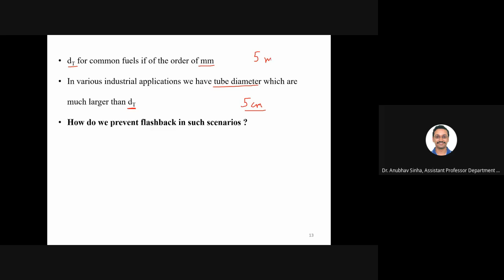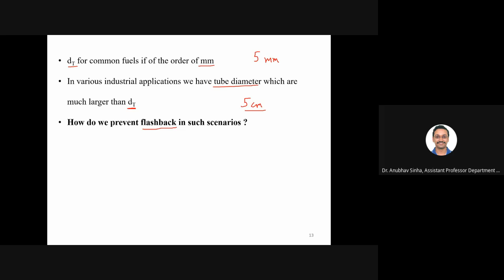So will it quench? Will a 5 centimeter tube quench where 5 mm is required? Yes or no? Yes, sir. So what will happen if I have a flame? I need 5 mm to quench that flame, but my tube is 5 centimeter, or let us say 50 centimeter. How do I prevent flashback? If I am not able to quench, it will flash back, right? You look at the video, same thing will happen. So what can I do? Cool the tube. Yes, you're going in the correct direction.